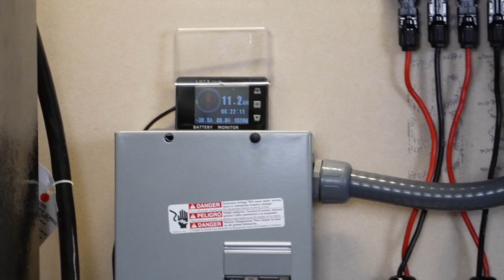Okay, I turned off the breaker to the EV charger. Now, so what we have here, we have 43.97 and climbing voltage, now up to 44. We do have a pack under voltage alarm, a cell under voltage alarm, and state of charge low voltage alarm. So all those was set.